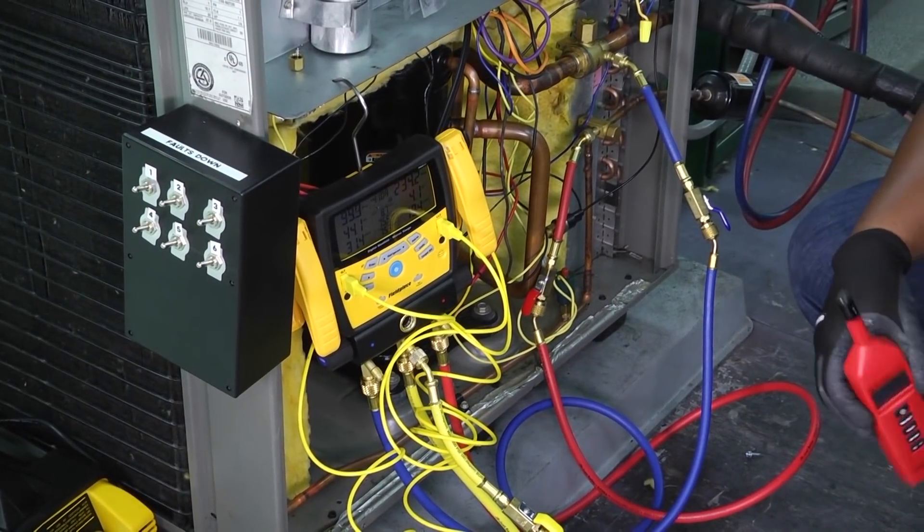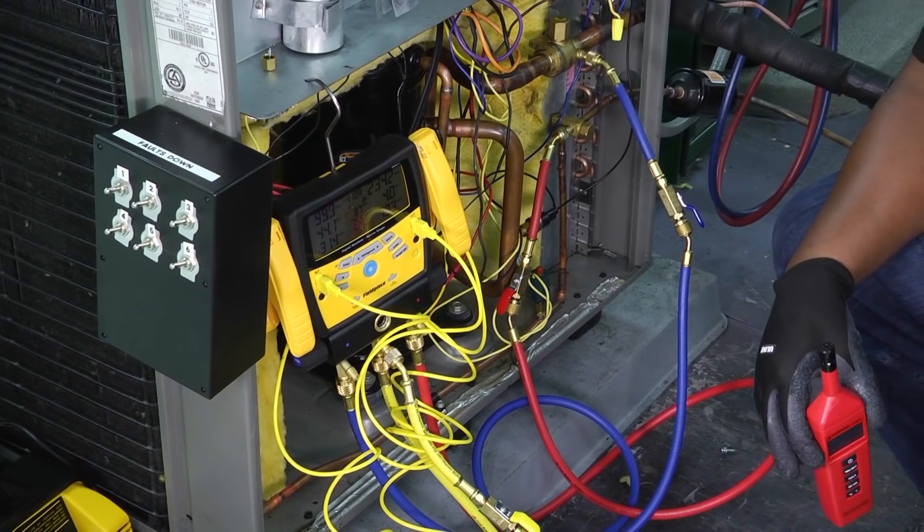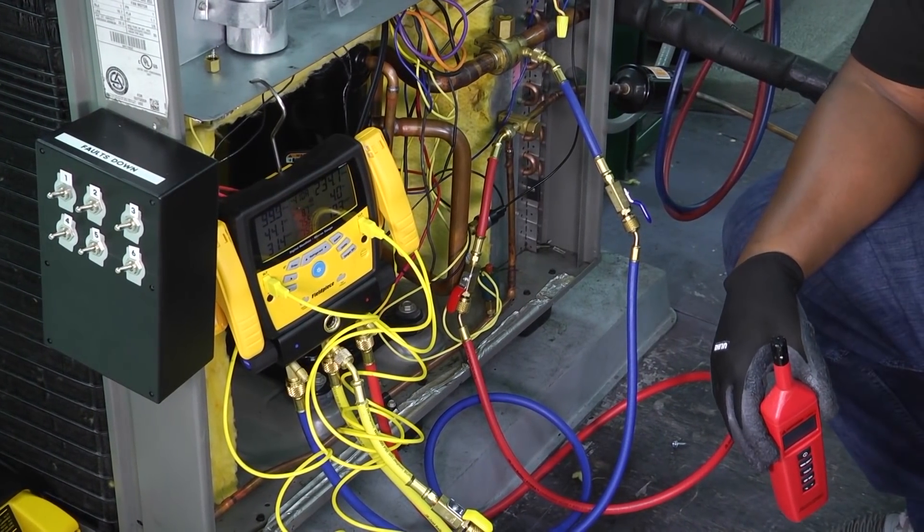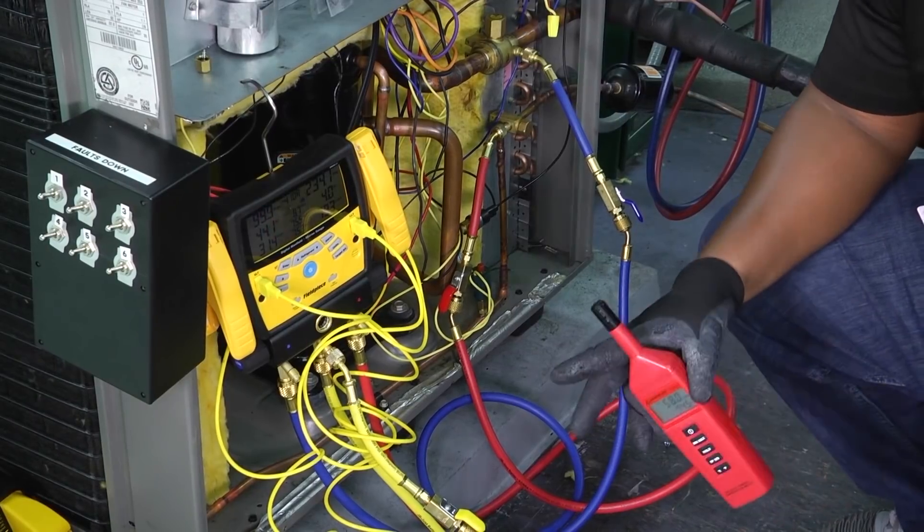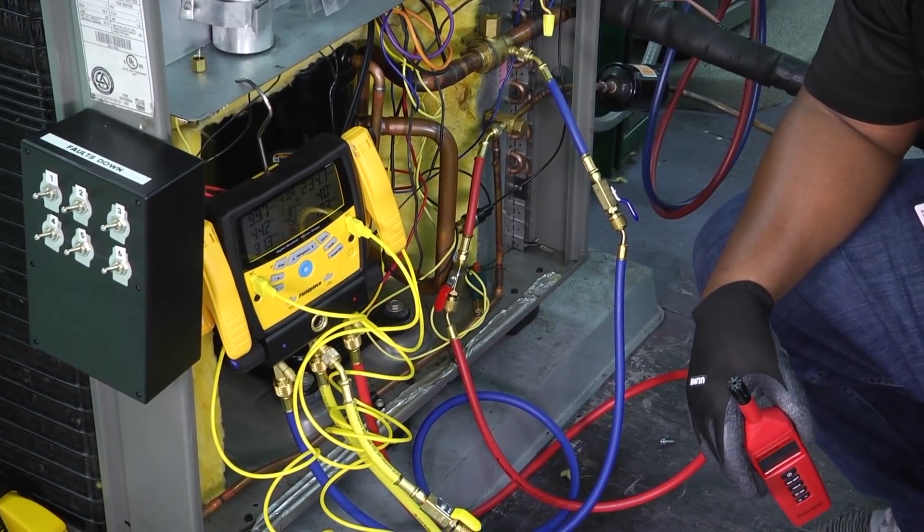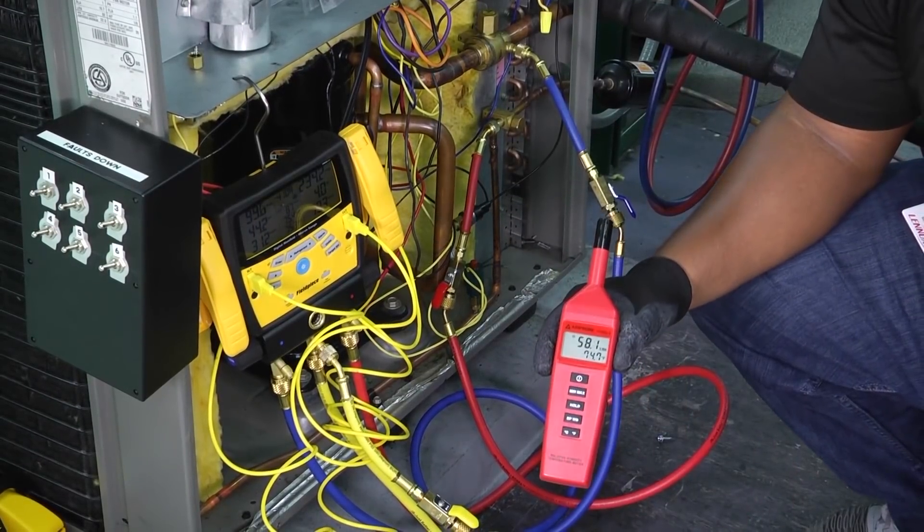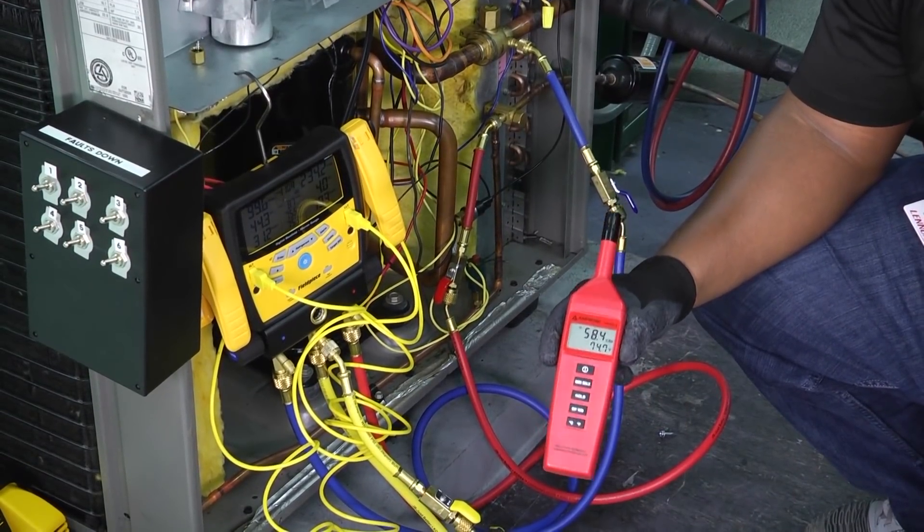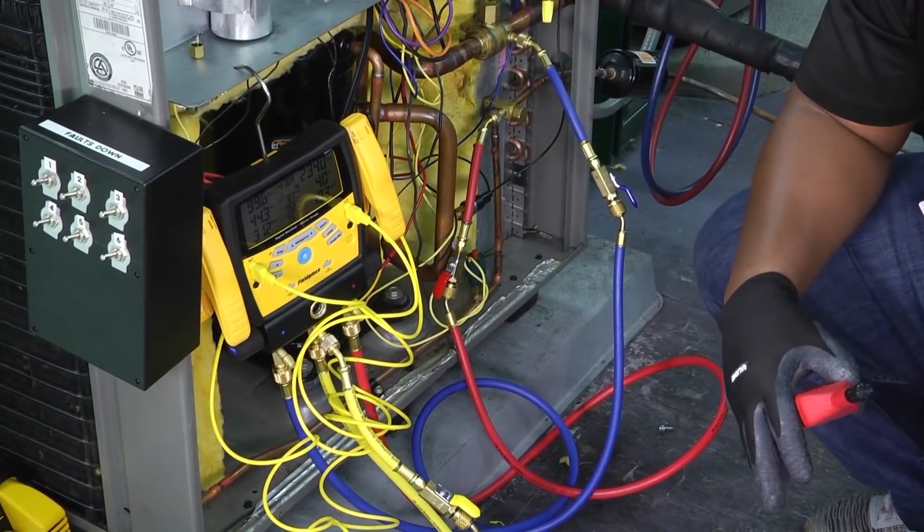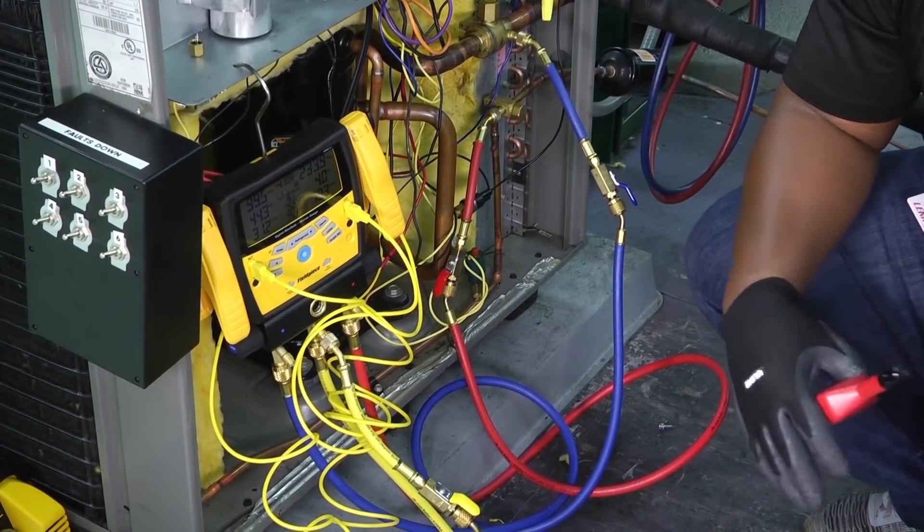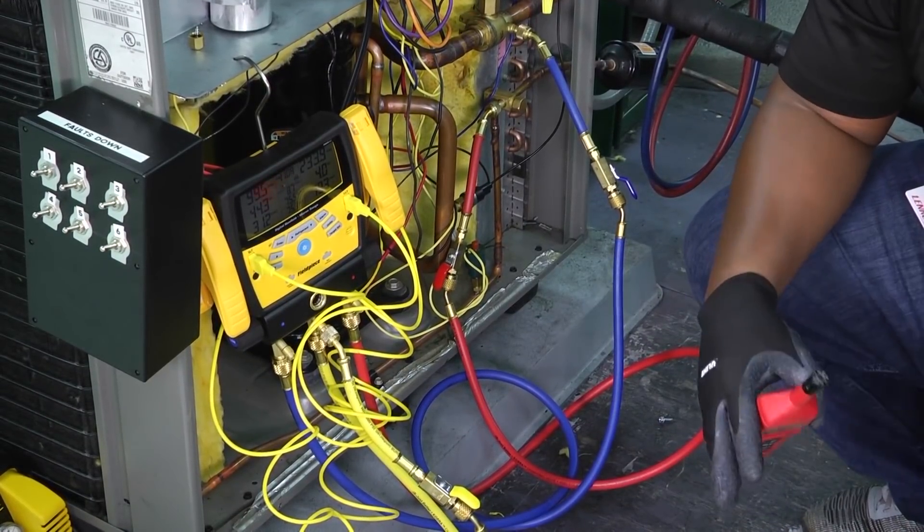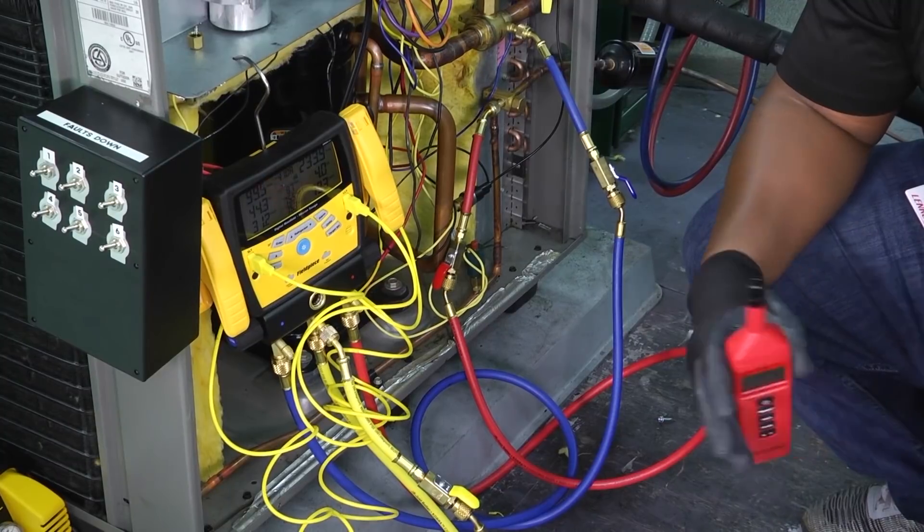So, just real quickly as we close, just a few things to remember when it comes to evaluating refrigerant charge. One, you've got to have your superheat and subcooling number. Number two, you have to know which type of metering device you have on your system. Number three, make sure you have a digital psychrometer so that you can calculate wet bulb temperatures. Number four, refer to any charts or manufacturer specifications on data tags to find the desired subcooling or superheat and subcooling ranges.